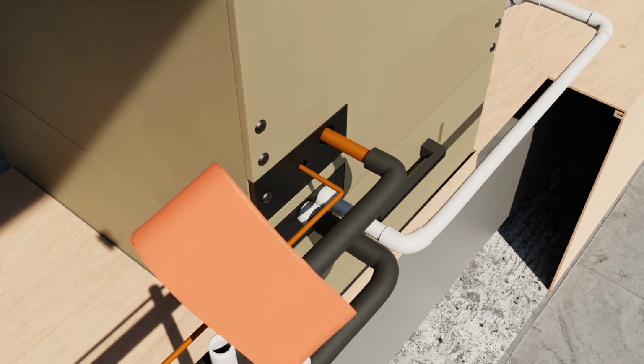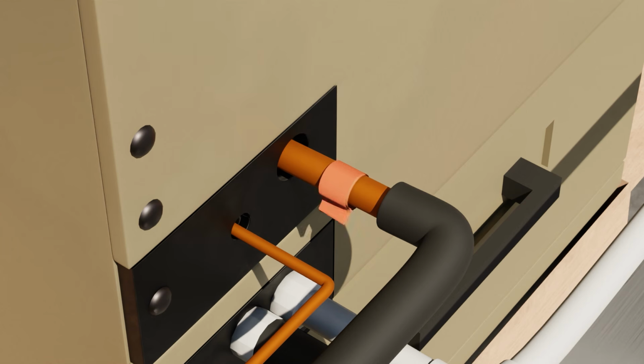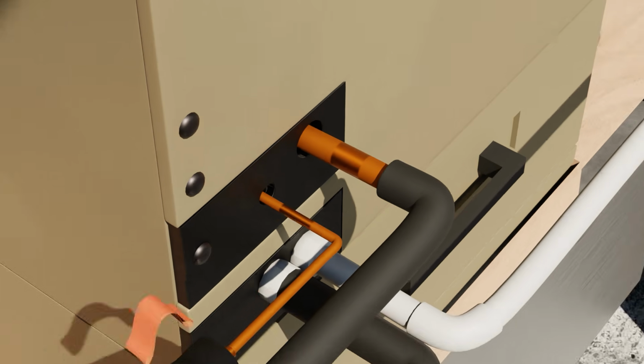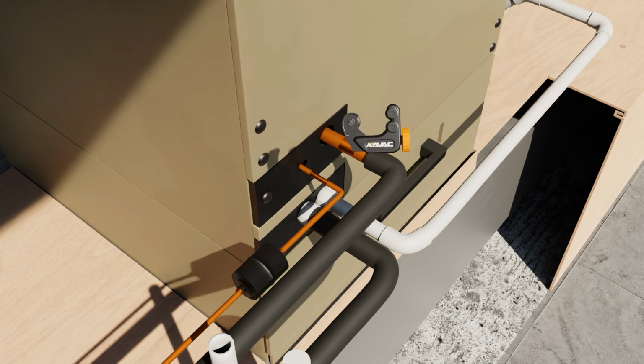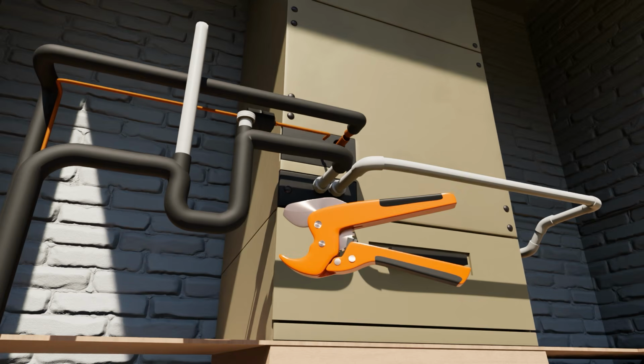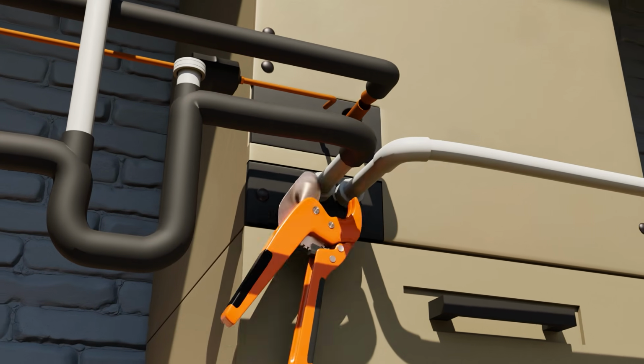When working with copper, one of your most important tasks is to ensure that no solid contaminants make it into the lines. When using a tubing cutter, cut the copper slowly with many rotations to ensure that you don't bend or oval the copper. Do the same on the inside and outside of the copper line set. Now you're going to cut the drain using a PVC cutter.